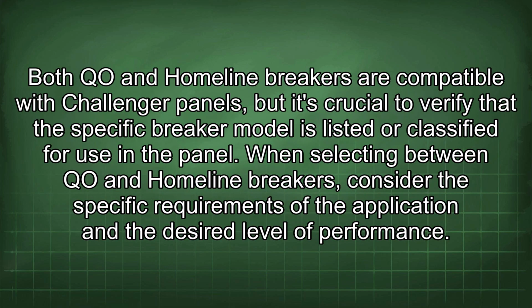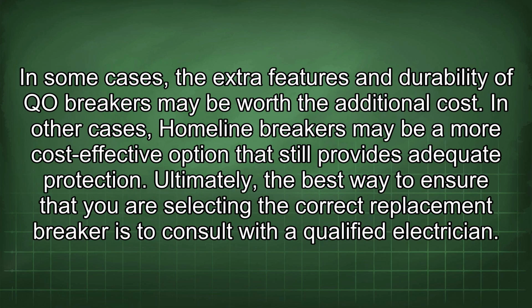Both QO and Homeline breakers are compatible with Challenger panels, but it's crucial to verify that the specific breaker model is listed or classified for use in the panel. When selecting between QO and Homeline breakers, consider the specific requirements of the application and the desired level of performance. In some cases, the extra features and durability of QO breakers may be worth the additional cost. In other cases, Homeline breakers may be a more cost-effective option that still provides adequate protection.